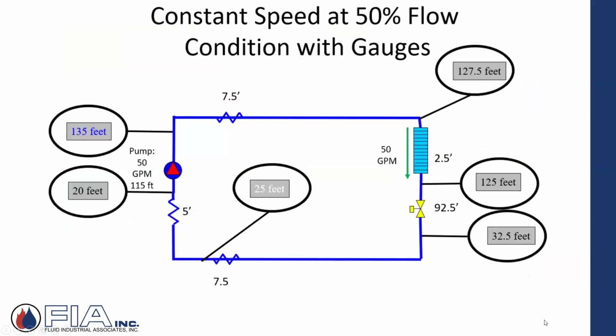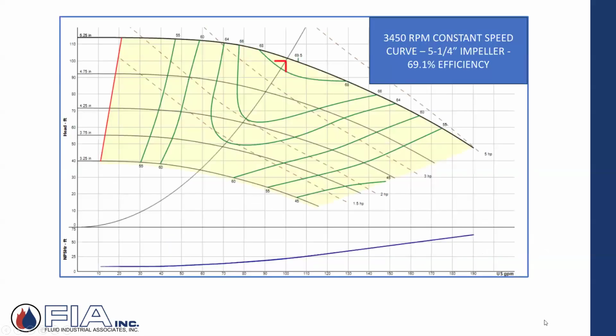And what we're trying to show here is, as the system conditions change, the valves close, not all of them, but to the point where I have 50% of that design flow. In this case, my pump is now back down to 50 gallons a minute. But in that constant speed application, look at the pump head. It's actually climbed to 115 feet of head. Why? Because it's backing up on that curve. Here's my 100 GPM at 100 feet of head.